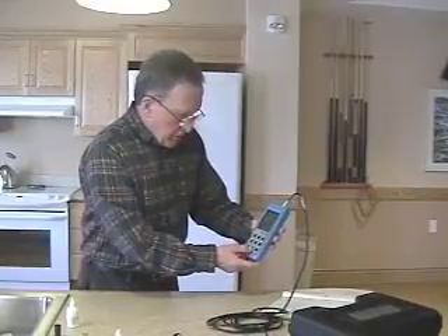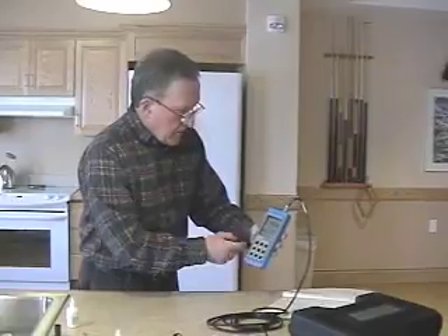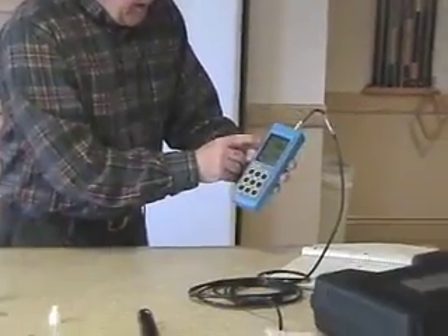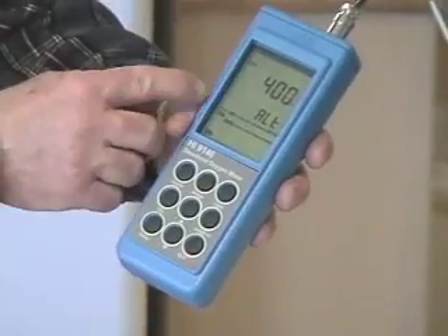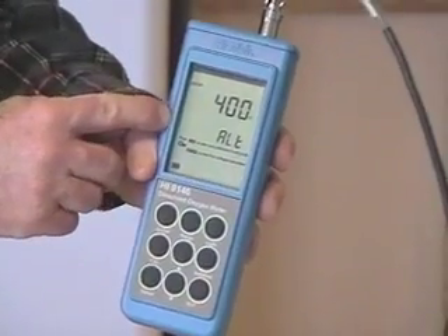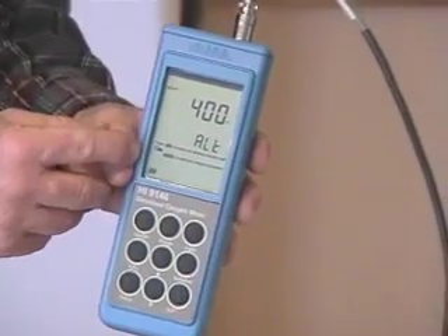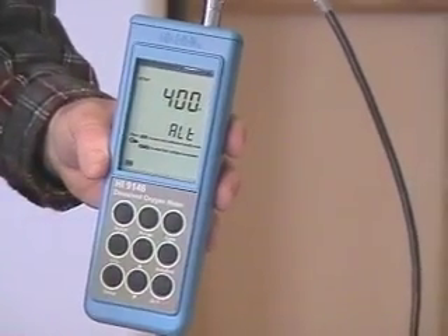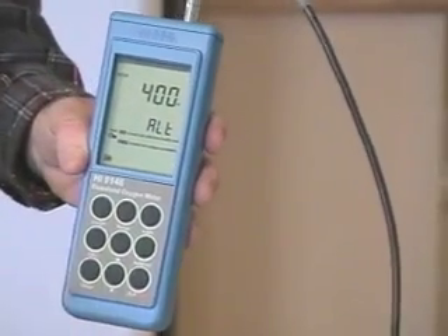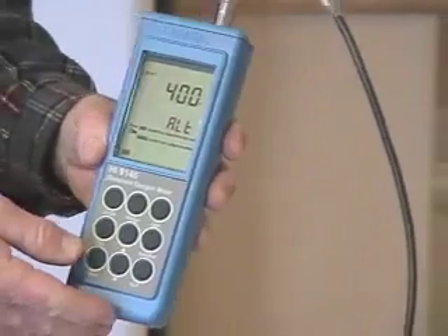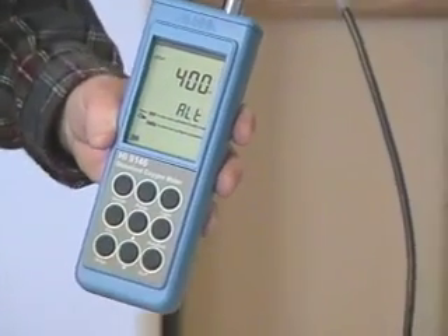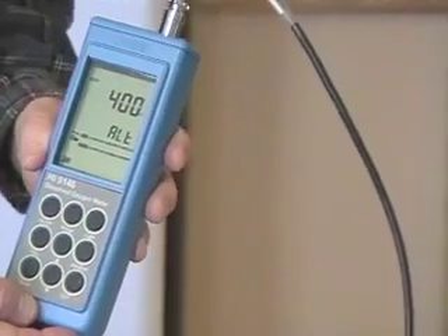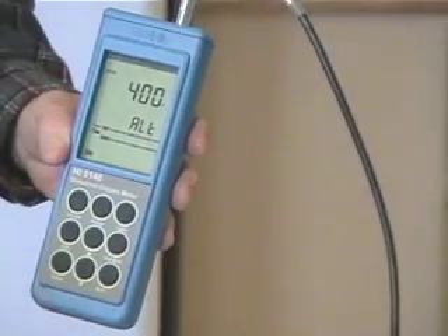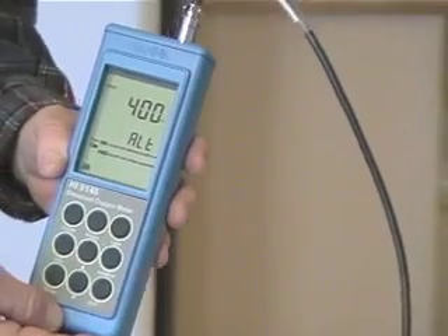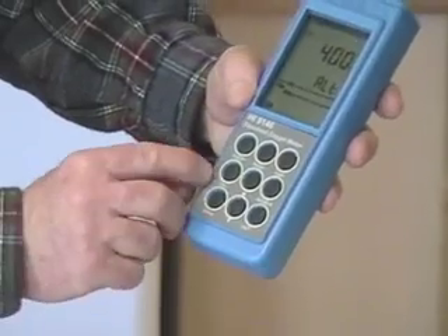So we're going to go to altitude. You push the up arrow. Okay, the altitude comes up. This meter has been used before, so the last time it was used, it was at a very high altitude, and the altitude is expressed in meters. So prior to your sampling, check out your altitude on TopoMap. It's expressed in feet. Convert that to meters. For our example today, let's say our sample site is at 600 feet. That would be approximately 200 meters. To change that, push the calibration button.